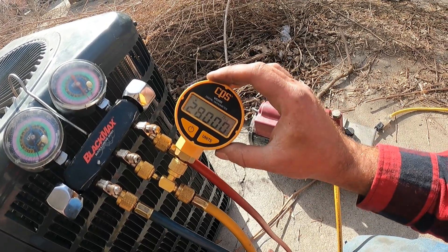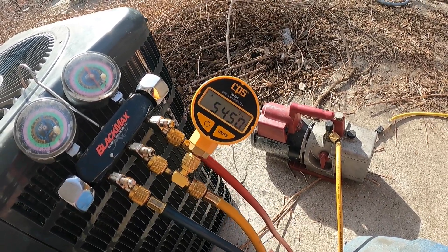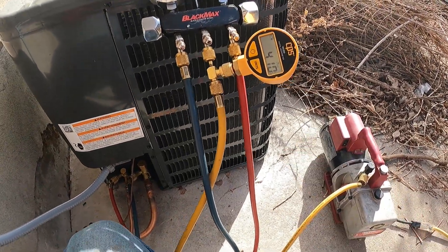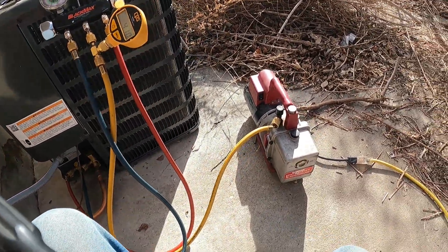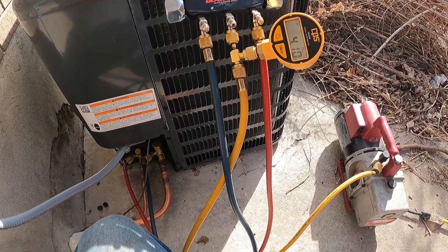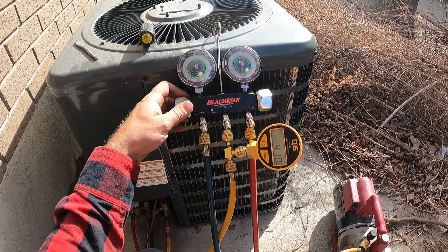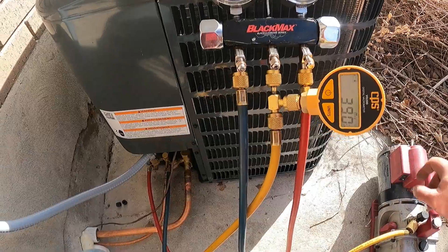Our goal is to get to 500 microns on this meter. It's been about an hour and we're at 410 microns, which means this thing is really pulling it down. This is a 6 CFM Robin Air vacuum pump — works extremely well, very fast. We're going to shut down our manifold knobs and shut off our vacuum pump.